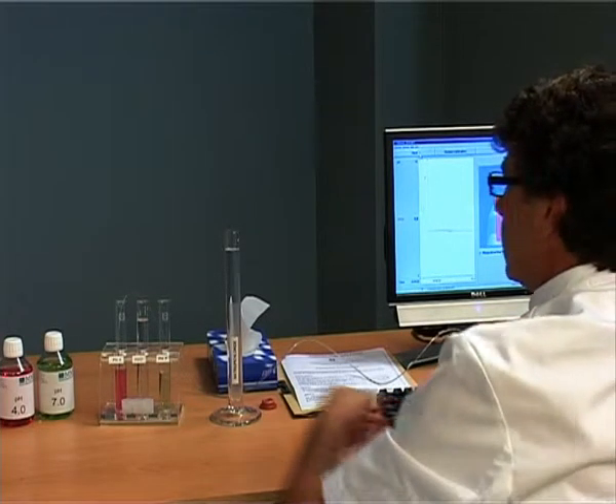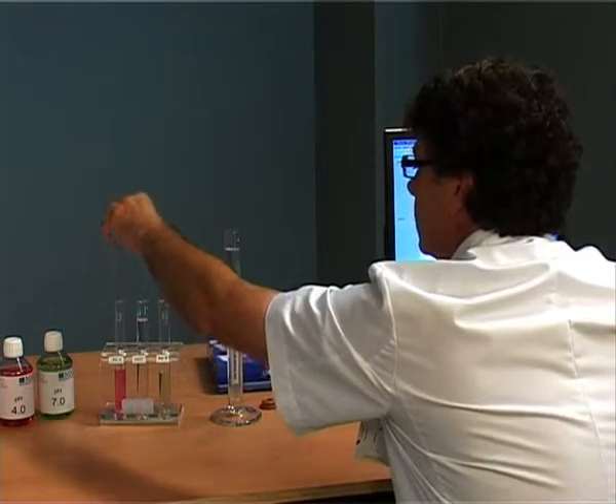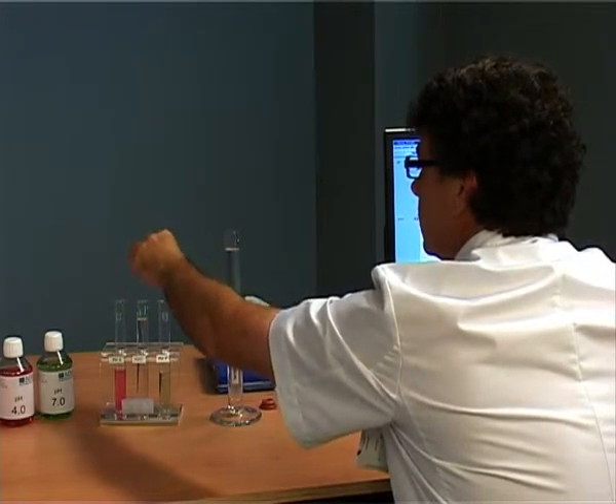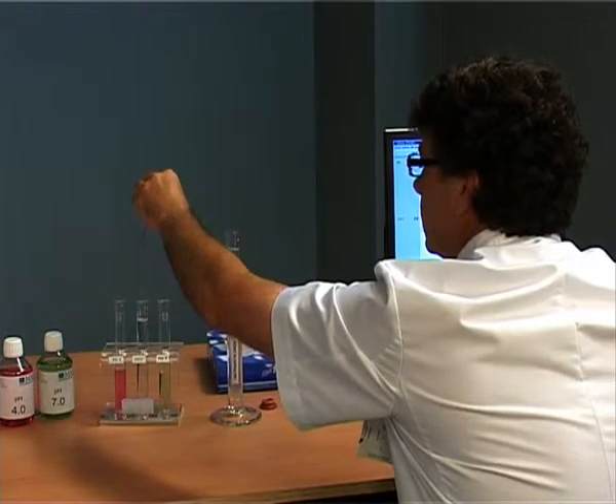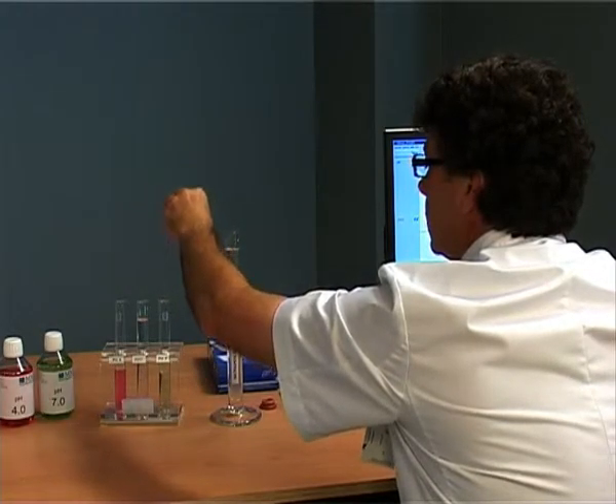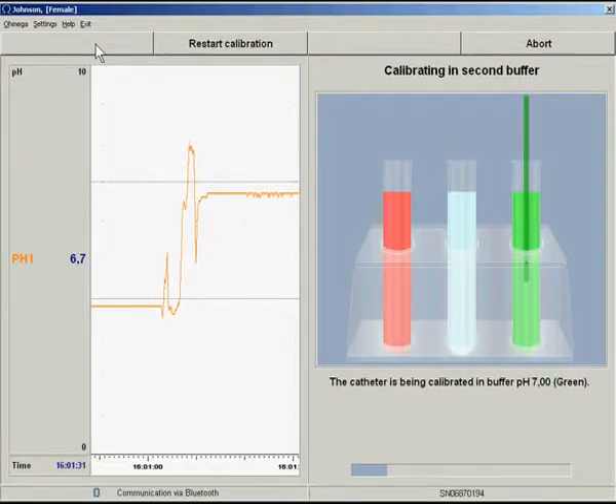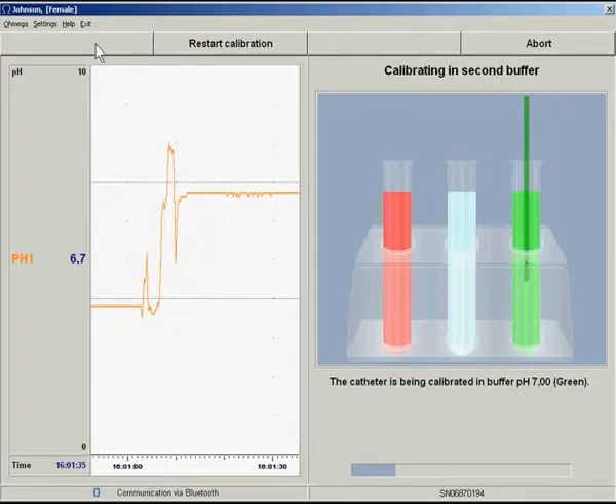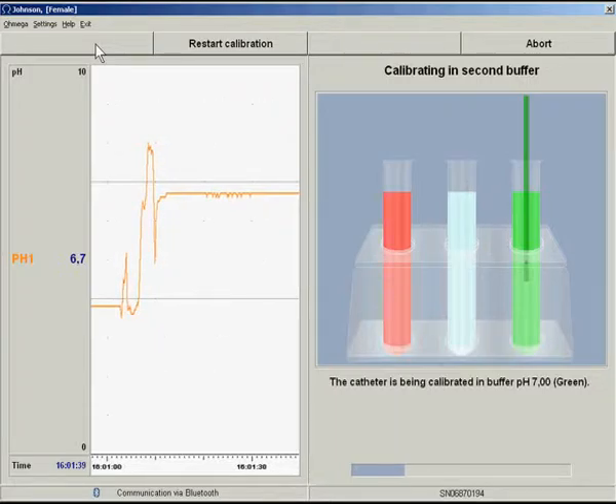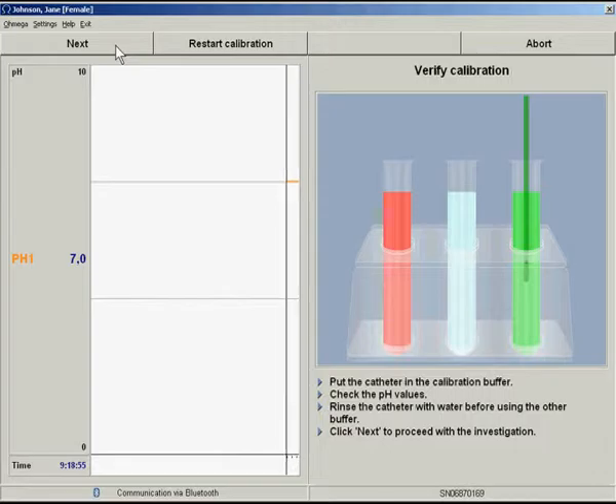Rinse the catheter with water. Contamination should be avoided as this can affect the quality of the calibration. Place the catheter in the green buffer solution pH 7 to continue calibration. When the pH 7 signal is stable, calibration ends.